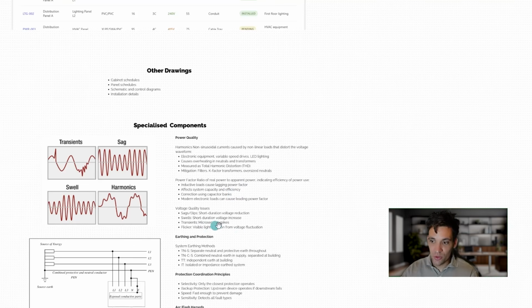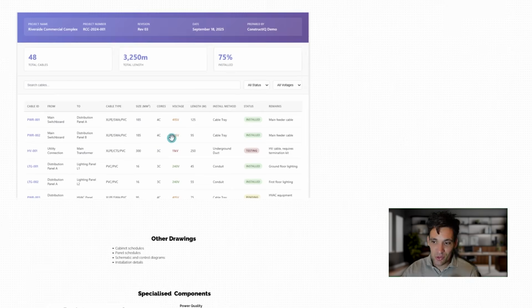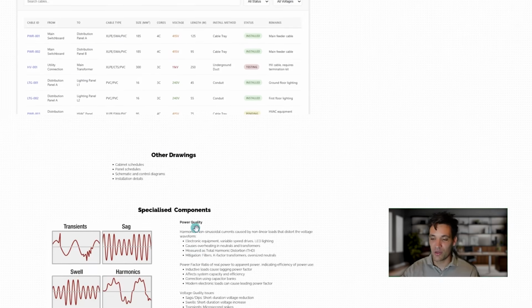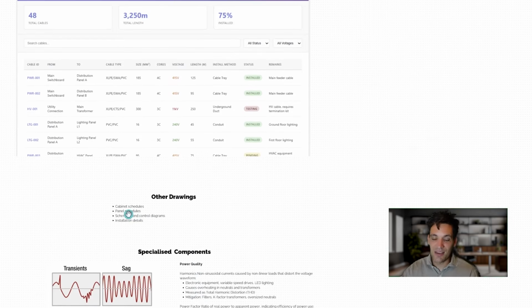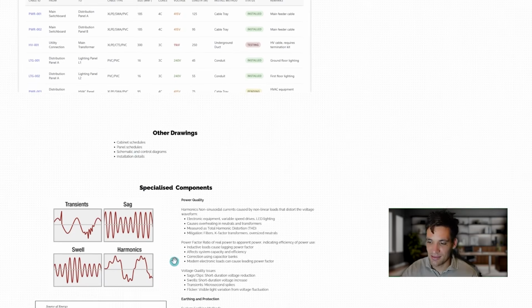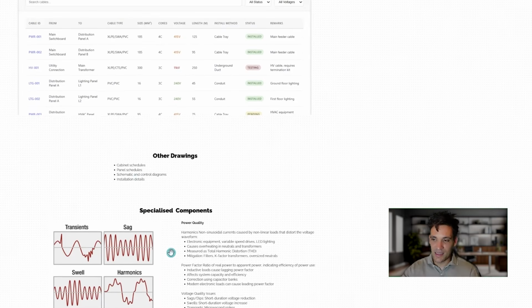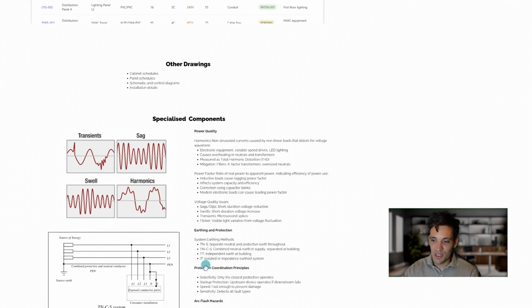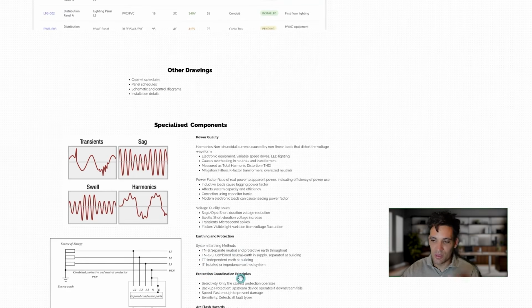We can also have voltage quality issues. That's why the cable schedule is such an essential document, because where you get voltage drop across long cable runs, we need to make sure we're measuring the lengths of the cables we're installing, and that we're installing the same lengths as in the cable schedule. If the lengths are different to the cable schedule, the cable is probably sized incorrectly. That's a big problem on construction projects where the designers haven't properly laid out the routes or checked the lengths, or we install it differently to how they intended, and we end up with voltage drop issues because we've installed a longer cable than planned.